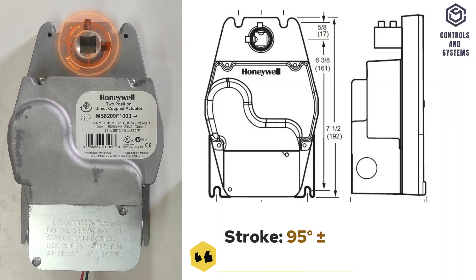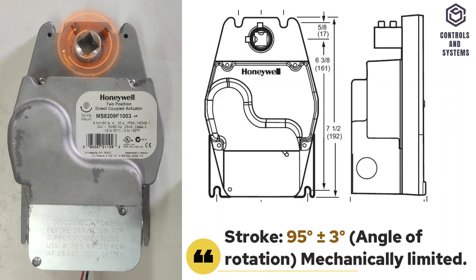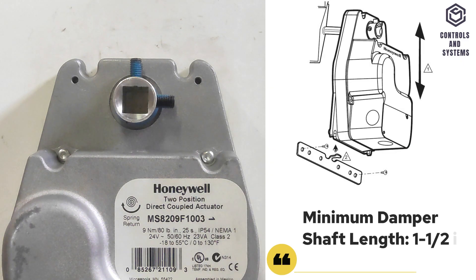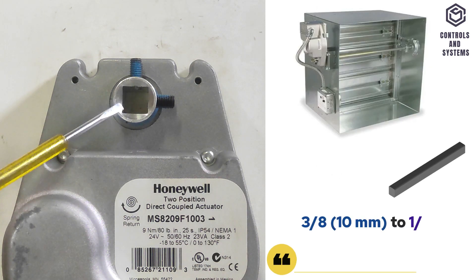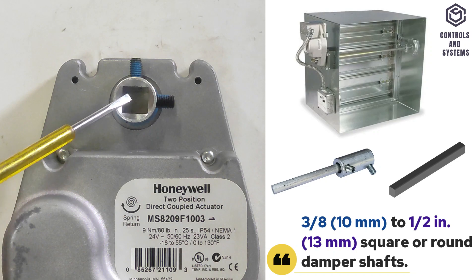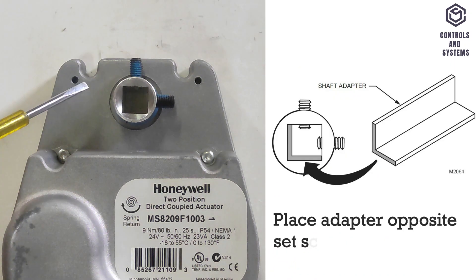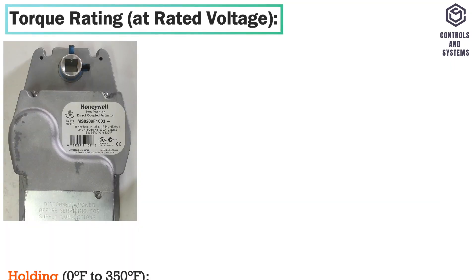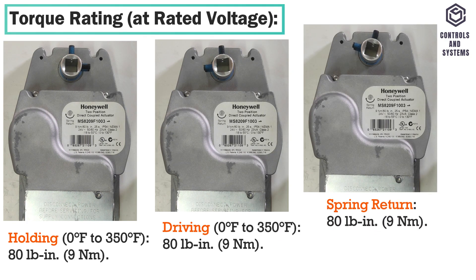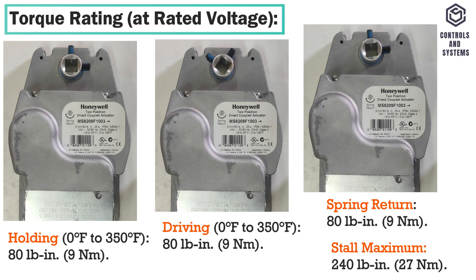Functional Data: The actuator has been designed to have a 95-degree angle of rotation. The spring return timing of the actuator is 15 seconds. Minimum damper shaft length is 38 mm. If the damper shaft is 10 mm round or square, use a shaft adapter and place the adapter opposite the set screws. Torque rating: holding is 9 Nm, typical driving is 9 Nm, spring return is 9 Nm, and stall maximum is 27 Nm.